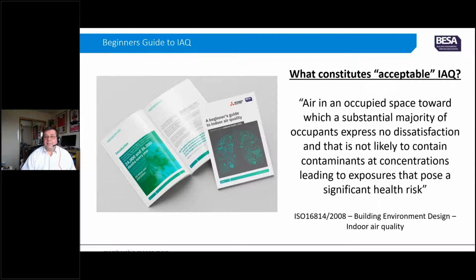Or thirdly, by the ventilation rate. From a design point of view, it's normally the indirect ventilation rate method that is used, because the designer can't know how susceptible the occupants will be to odours, etc. The installation of sufficient ventilation by design will be seen as a measure of ensuring that the health measurement doesn't come into play.